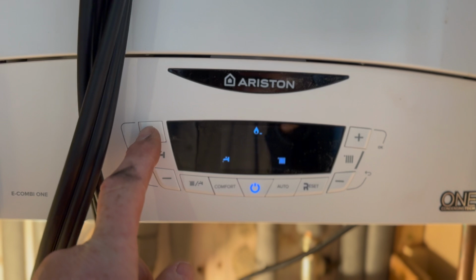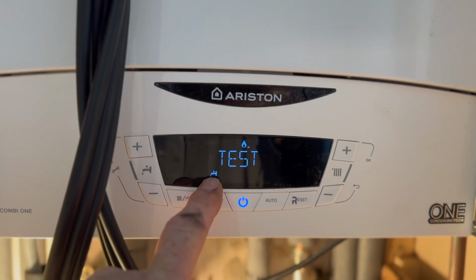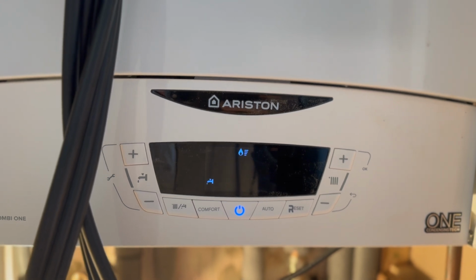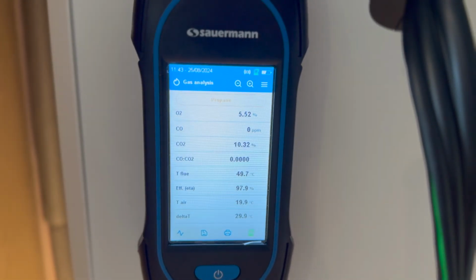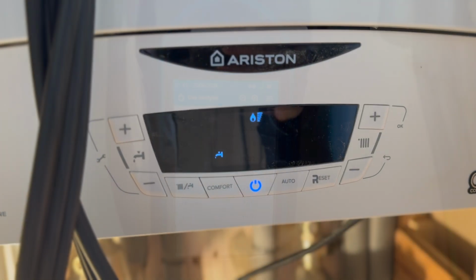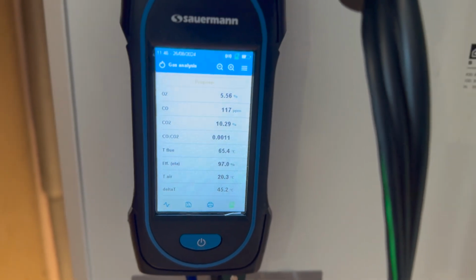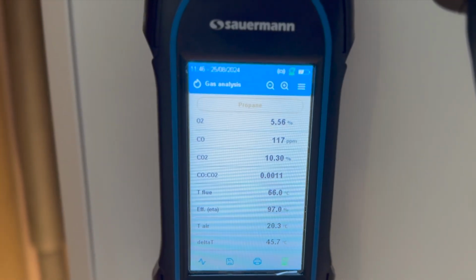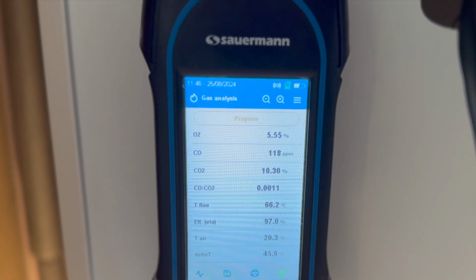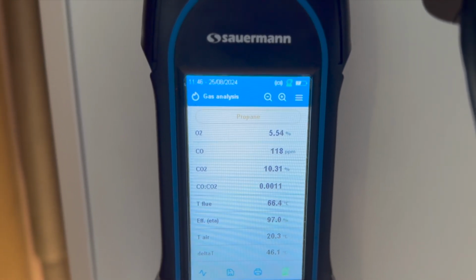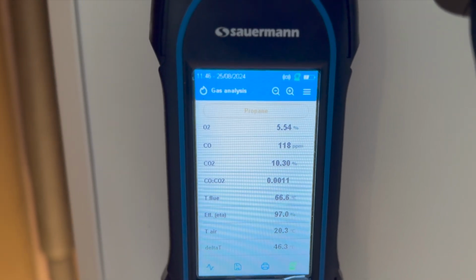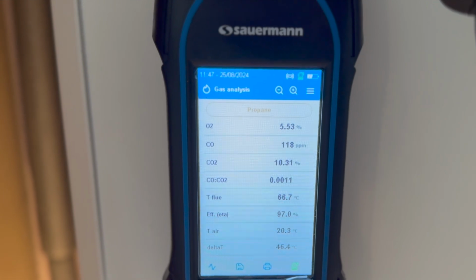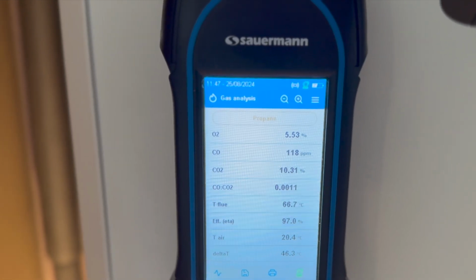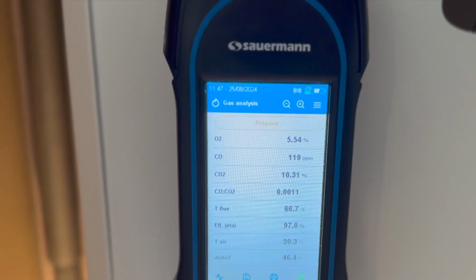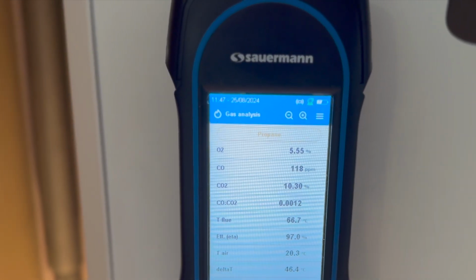So let's put this into maximum. The way we do that is press the plus button so we just get the tap symbol on its own. It'll now go into high fire. We can now take the readings once it's settled down. So let's check. Now we're on high fire. Let's see what we've got now. So we have an O2 of 5.5. We now have a CO of 118. We now have a CO2 of 10.31. And we have a ratio of 0.0011. So put down in the comments, guys, if you think that is tickety boo, or whether I should adjust the gas valve or not.